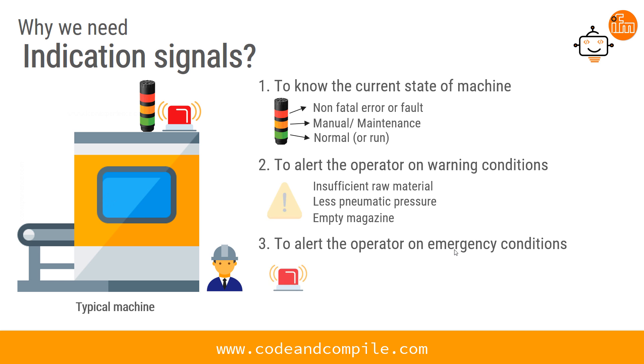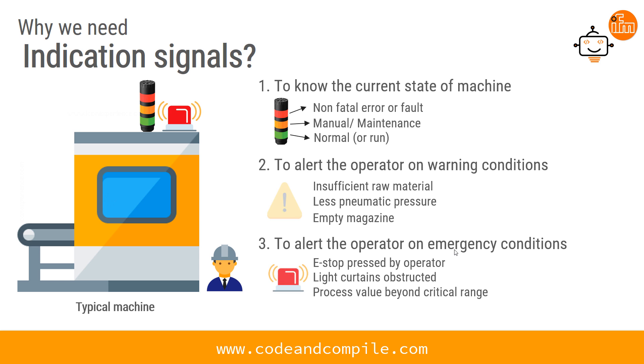The third reason is to alert the operator on emergency conditions, generally done by a buzzer. Emergency conditions could be an e-stop pressed by the operator, obstructed light curtains used for safety, or a process value going beyond a critical range such as over-pressure or over-temperature.